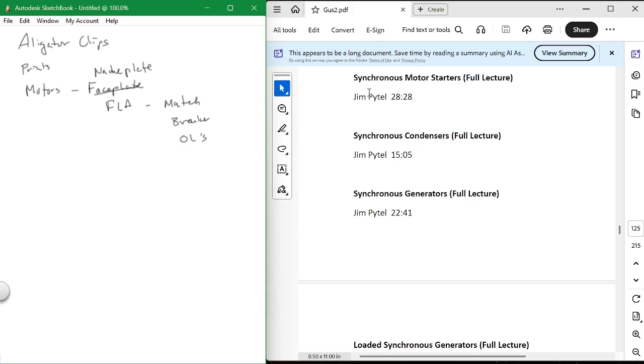But basically what you're looking for is, do I have the right size breaker, and do I have the right size overloads? Or do I have to go back? Now today, most overloads are settable in the field, and you can actually set them. The older style overloads were already set to a certain value, and you had to match them. So you had some extra ones someplace, but the overloads had to match exactly the motor overload current that you wanted, okay? So if the full load amps was 20, you would want to go with 21.5 or something like that. You want to go a little bit above, but not much above what their rating is.